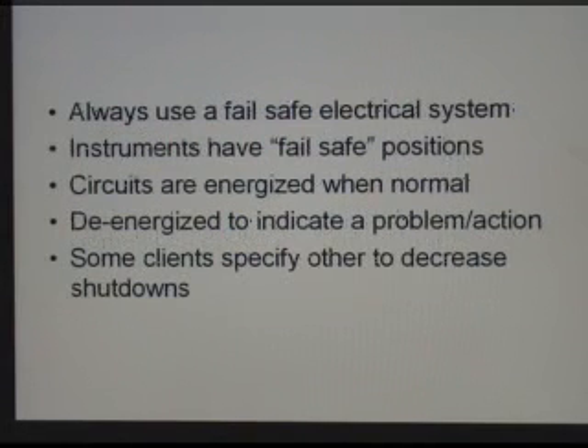We always use a fail-safe electrical system, which means that all the instruments are going to have a fail-safe position, and the valves will be spring-loaded to go into what we consider the fail-safe position. If it's a process valve, it'll be fail-closed. If it's a lube oil control valve, it may be fail-open to make sure that we have enough or more than enough oil getting to our bearings. The circuits are energized in normal operation, and they're going to be de-energized to indicate that there's a problem or that an action needs to be done.